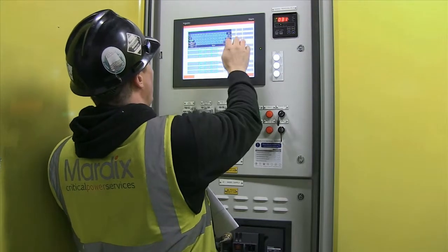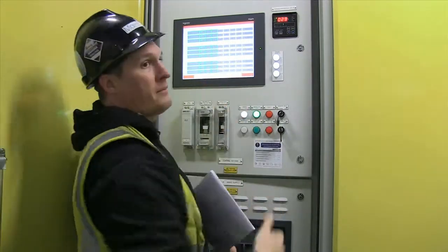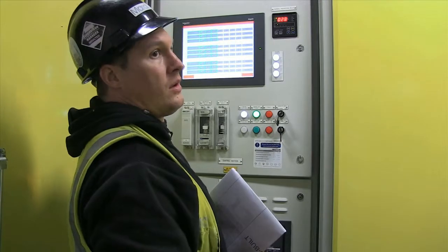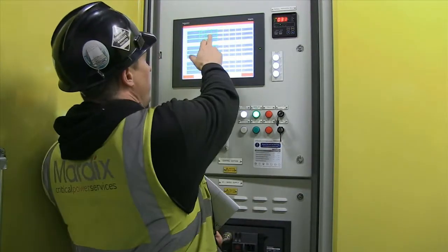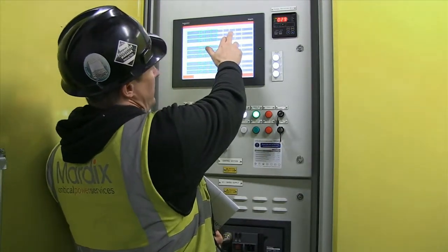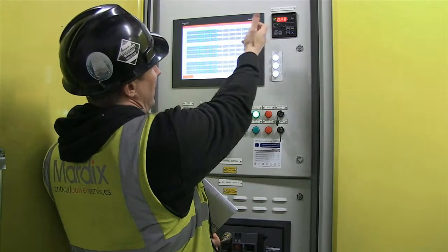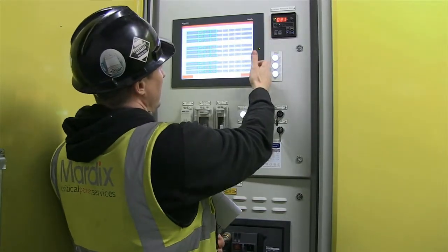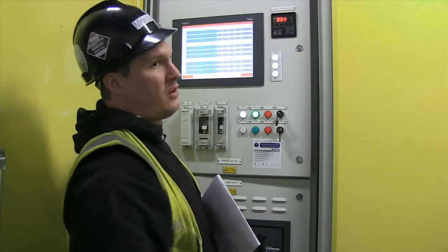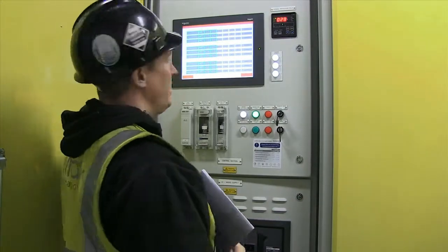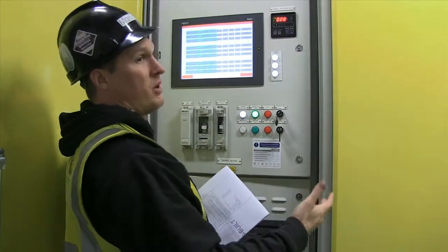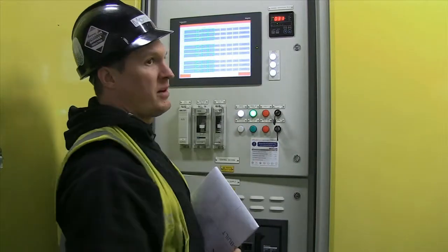What parameters are you monitoring, Matt? On the outputs, what are you monitoring? Just load? Yeah, we're monitoring voltage, current, and obviously from that, you can get kilowatts and kVA, kilowatt hours, so you've got a total kilowatt hours reading down there. That's it. It's not going to give you anything like what you're going to get from an ION meter, but for metering purposes, for billing purposes, essentially, you've got the information that you need on there.